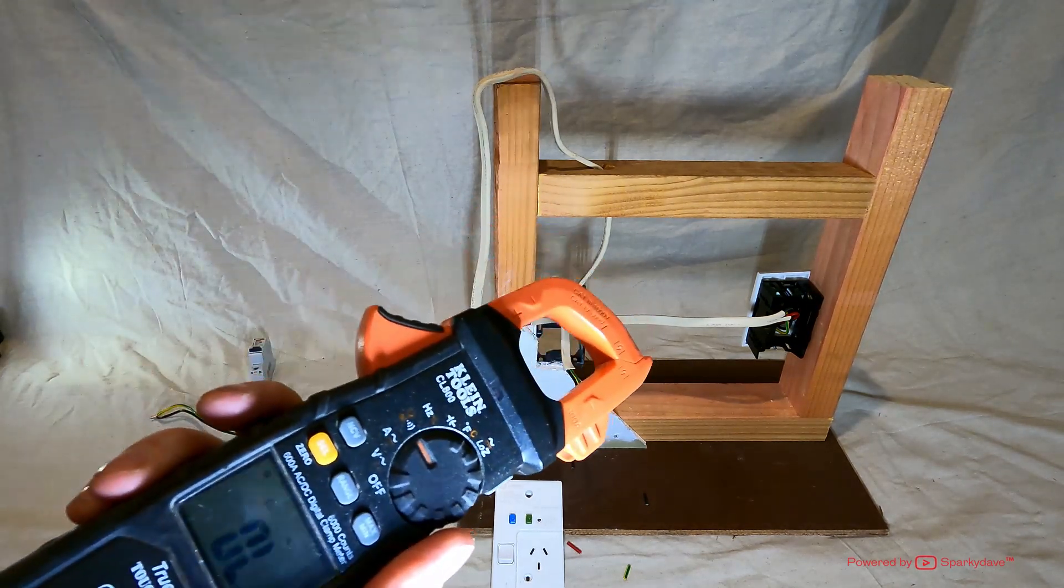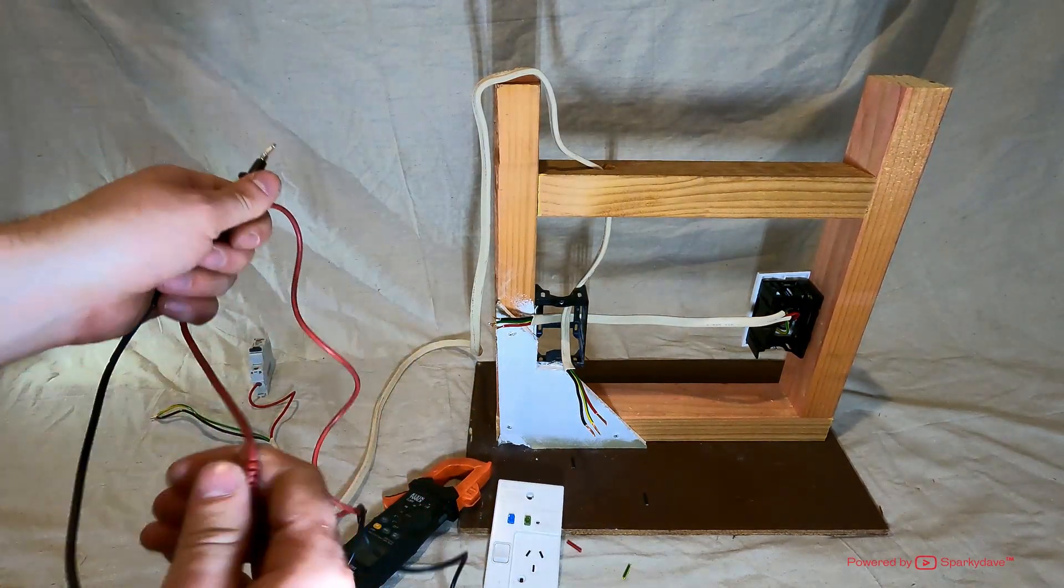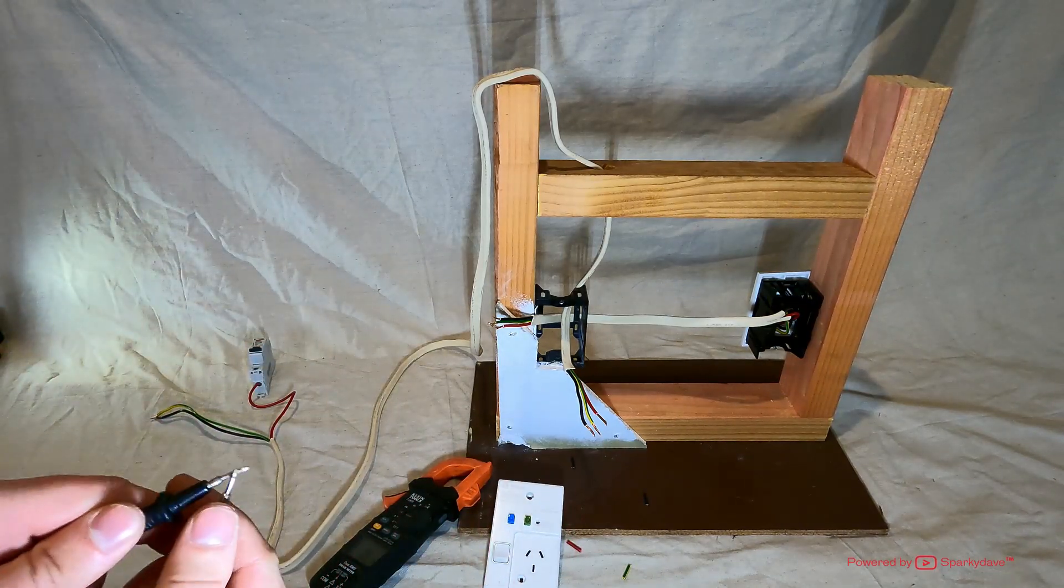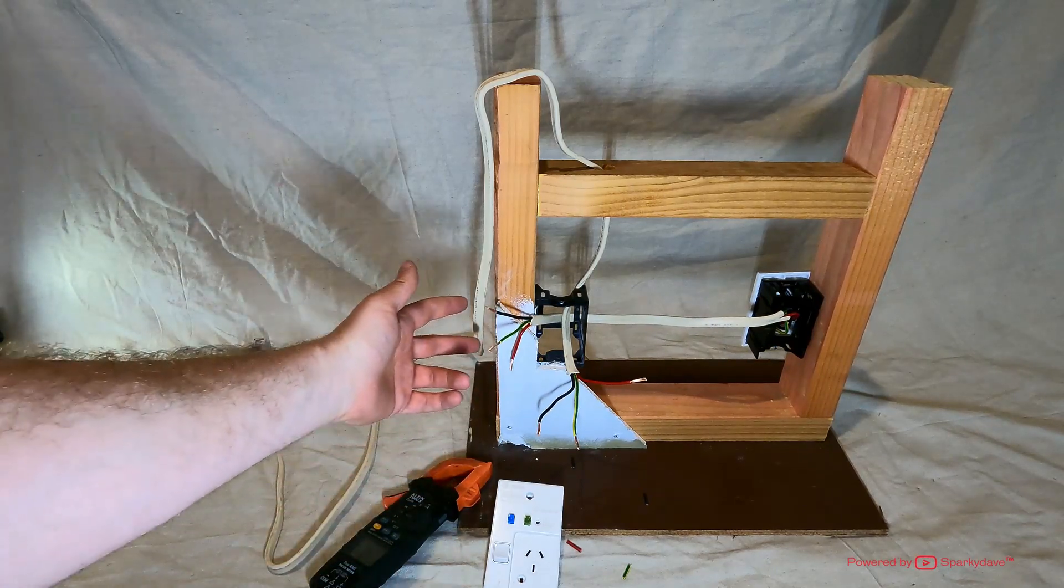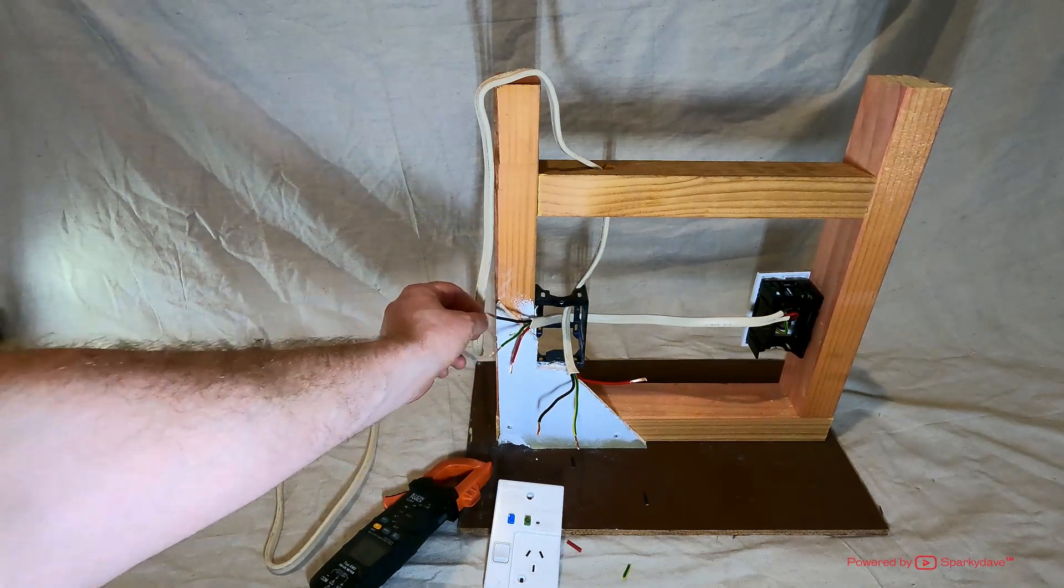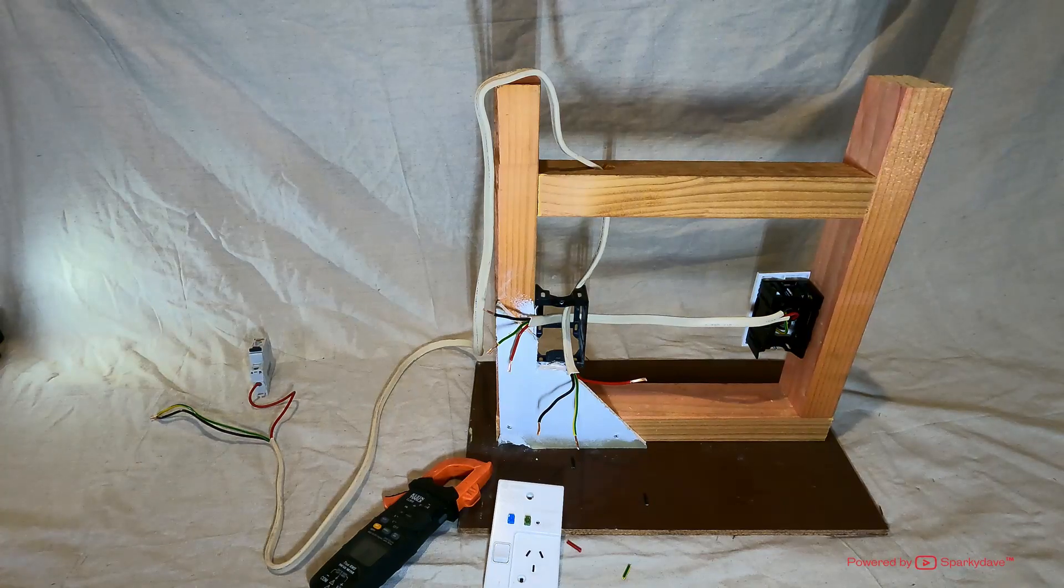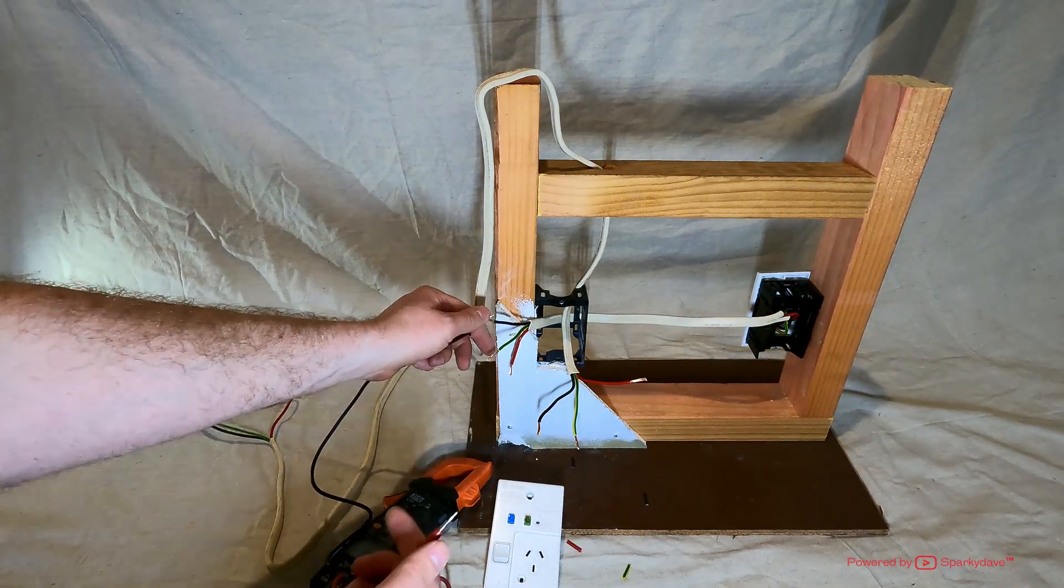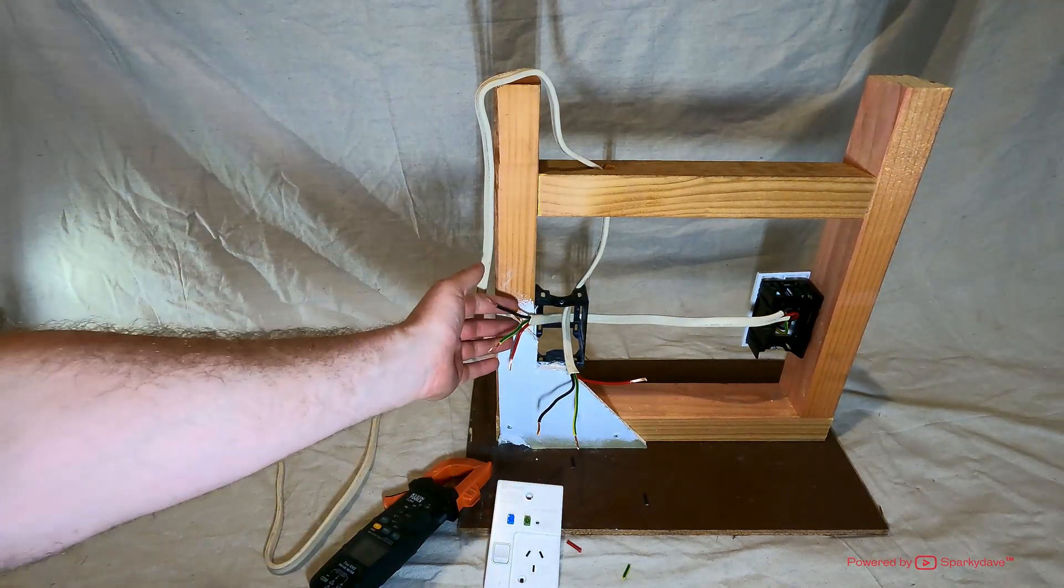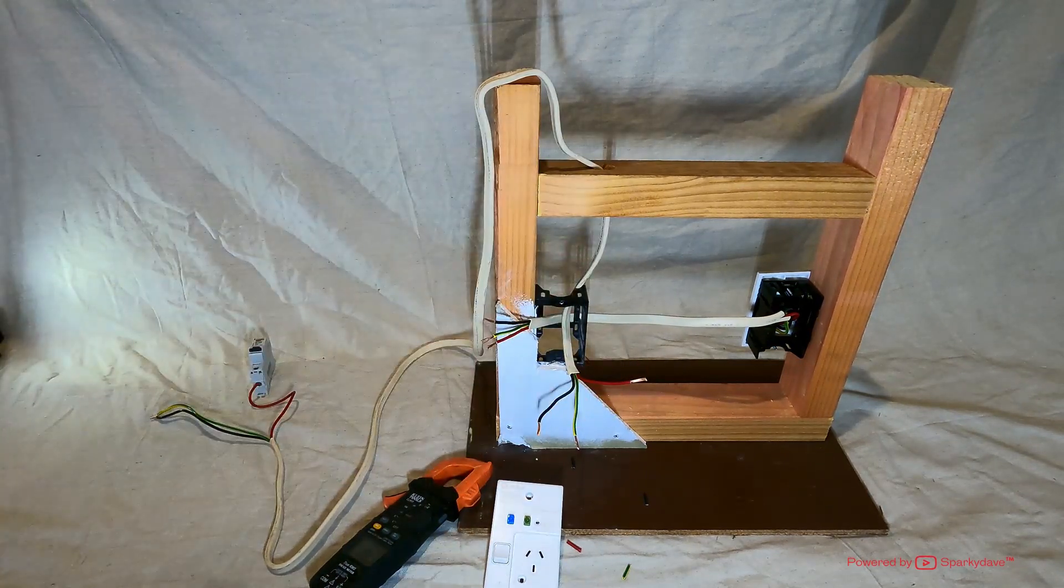It should be on continuity, which means that when you put the two leads together, it will beep. I hope you can hear that. Now we spread the ends out and we're going to be testing between the earth and the neutral, so the green and the black cable cores of each cable, to determine which one actually goes back to the switchboard. If you put it between the black and the green and there's no beep, that means that cable does not go back to the switchboard and it will be a load cable going to the next socket outlet.